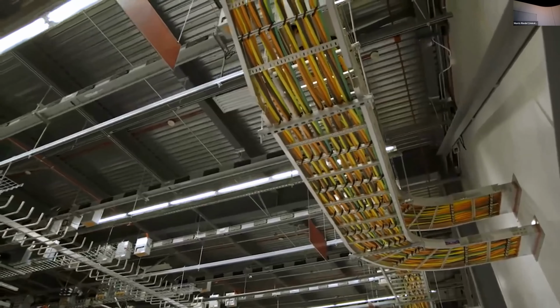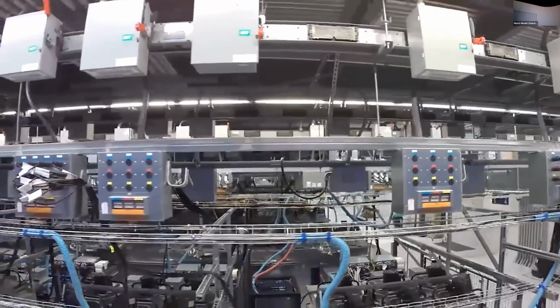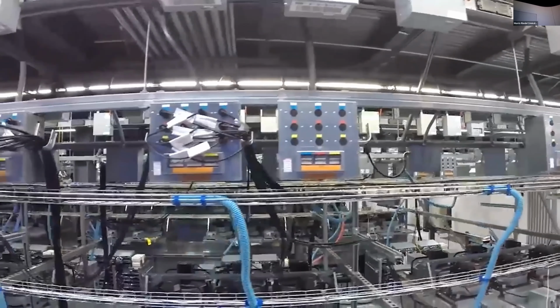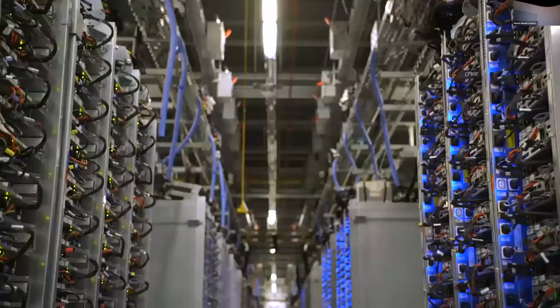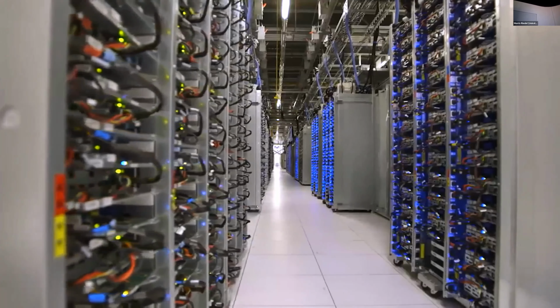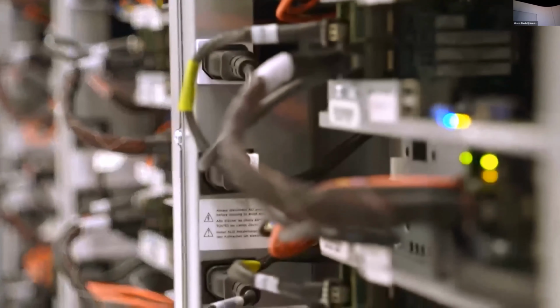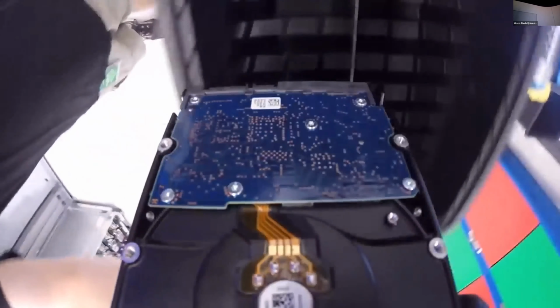distribution. Coming from the outside yard, we bring in the high voltage power distributed across the bus bars to all of the customized bus taps that are basically plugs where we plug in all the extension cords. All of our racks don't really look like a traditional server rack. These are custom designed and built for Google so that we can optimize the servers for hyper efficiency and high performance computing. It's true that sometimes drives fail and we have to replace them to upgrade them because maybe they're just no longer efficient to run.